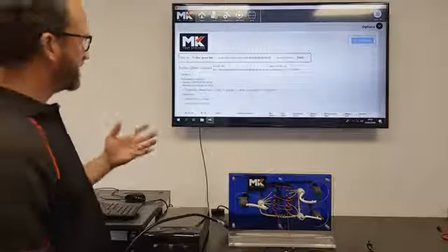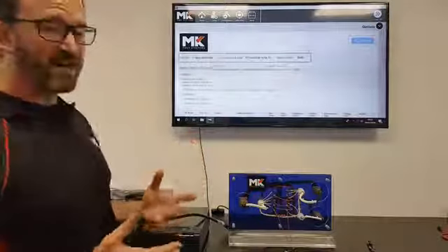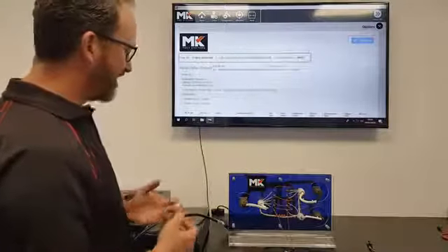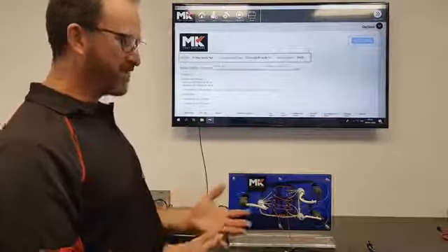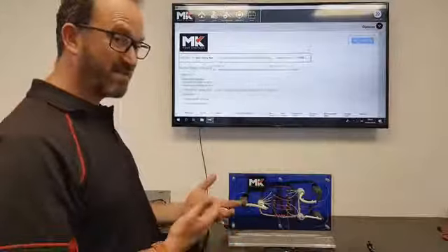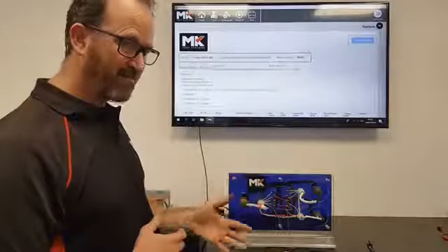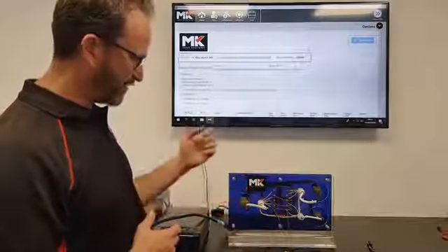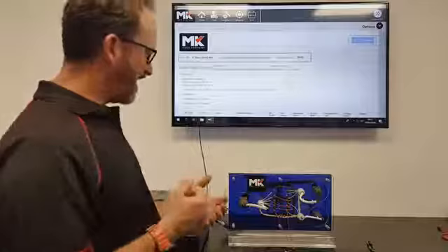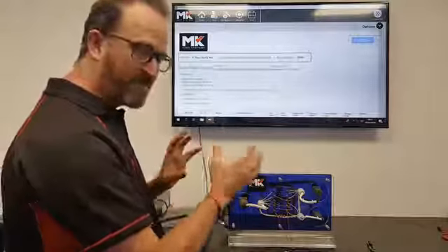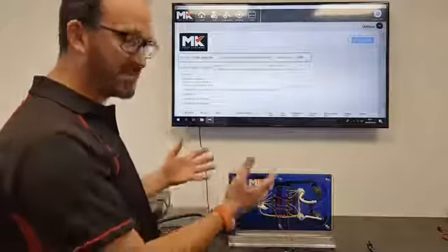So we have a look again at this test report. We can see that the test took around 18 seconds to run, so very, very fast. And what did that system test during that process? It made 11 continuity resistance measurements, accurate to milliohm, so very, very accurate. It ran a short circuit test across all the test points within that range. So we've got 11 connections, so 11 times 11, 121 measurements to check for any short circuits during that process. Very, very fast, and it took a second to run all those tests.